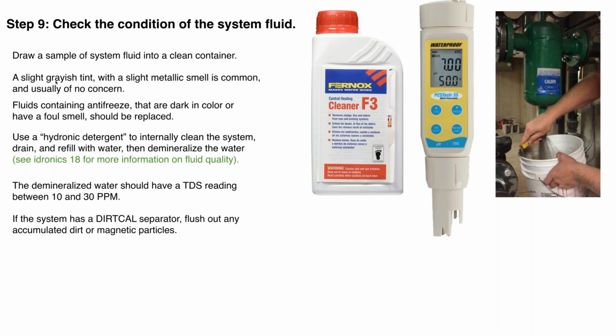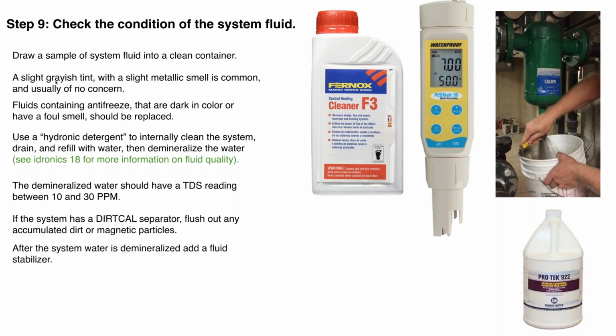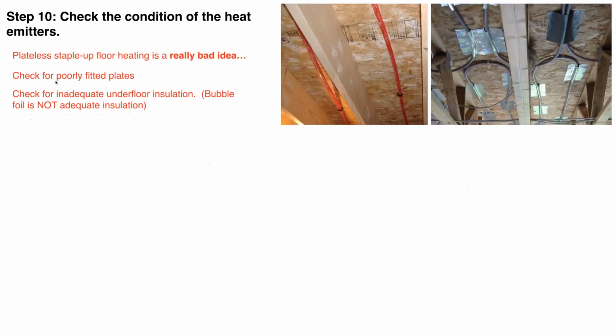And if you've got a dirt separator in there, especially with a magnet in it, obviously giving that thing a periodic flush and seeing what comes out. You can see here there's quite a bit of magnetite coming out of that system, especially if it's an older system. Maybe it's an old steam system that's been converted over to hot water. Okay, and add a system stabilizer. That will preserve the pH of that water.